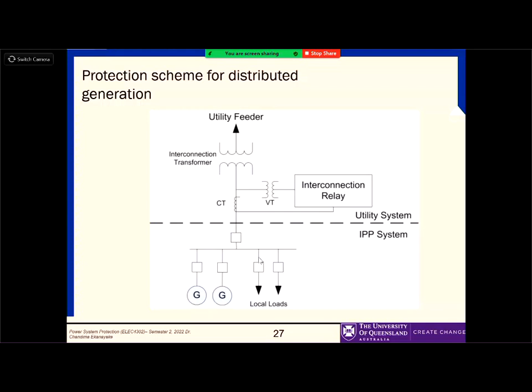So the generators here need some sort of protection schemes, as do sometimes these local loads. We talk about the short circuit current: what will be the magnitude of the current if there is a short circuit around this area? That current will increase if you have these generators. Therefore, sometimes your circuit breaker capacity has to be increased, right? Those sort of things we will discuss in the latter part of the course.